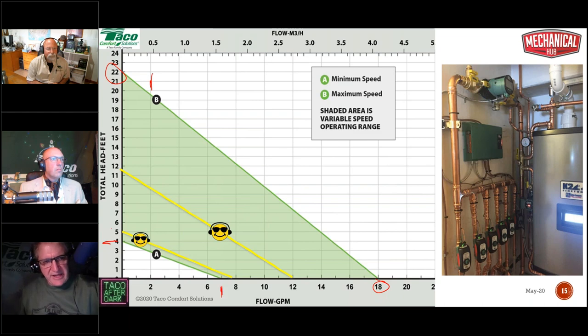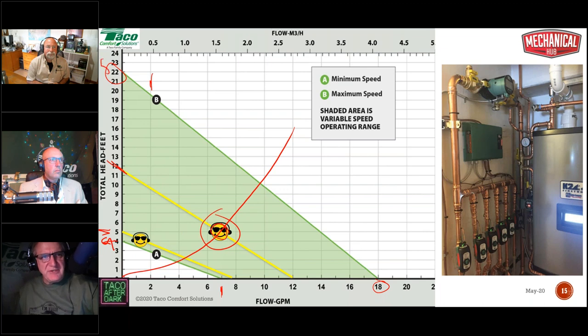Here we are, 7 gallons a minute at 5 foot of head, right there. There's the circulator, it's going to operate right there. Your system curve is going to go up like that, and bazinga, it's operating at 7 at 5. This is the maximum speed, and it looks like it's about 50% of the total. This thing goes from 9 watts up to 59 watts, so that might be about 30 watts right there. That's the fastest it's going to go.